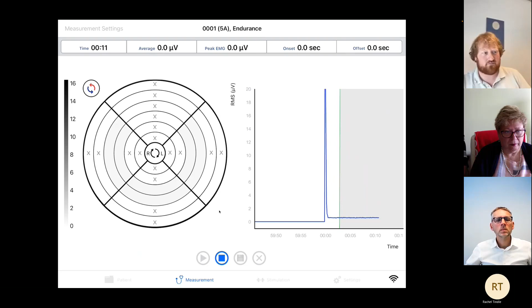Now, if I start the measurement again, the system does a number of safety checks. So it sets the zero potential of the body. It does the initial measurement of all EMG signals of all active electrodes, and it shows the average EMG of the active electrodes. Now, if this was an actual human, and this patient has, for example, more activity on the puborectalis, the line graph and the average EMG of the line graph would be much higher, because that's what we saw in the rest measurement, for example. And this is then what you would see in the line graph as well.